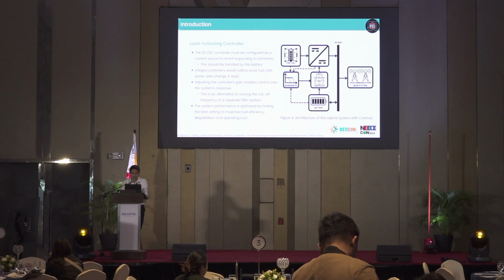What we propose is to use a load following controller, which instead of the standard cycle charging approach, has the fuel cell follow whatever the output demand requires. Of course, you don't want it too fast, otherwise it will degrade too fast. So the DC-DC converter must be configured as a current source because the battery will maintain the bus voltage.